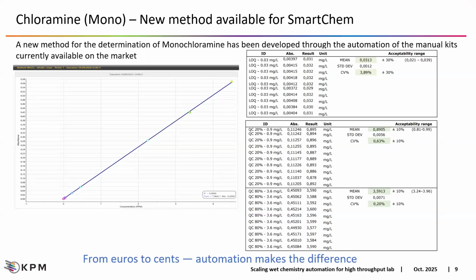Yes. So we are also working with the customer in automating manual kits today available in the market. This is one of the most successful cases: the possibility to automate the monochloramine testing from the manual kit available in the market today. In this case, we can really go from euros to cents. Why? Because with the actual manual kit, it is possible to run just one sample with one reagent powder, while automating the kit on SmartChem with one reagent powder, we have been able to run up to 50 samples. It means that a lab can reduce the cost of the kit 4 times. So still using the same kit, but by automating on SmartChem, they are saving a lot of money.